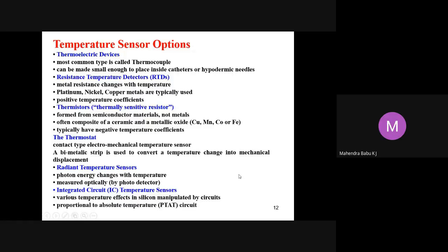When it comes to different types of temperature sensors, the options available for us are, first, thermoelectric devices. The most common type is called a thermocouple, which can be made small enough to place inside catheters or hypodermic needles. Then resistance temperature detectors, RTDs, where the metal resistance changes with temperature. Platinum, nickel, and copper are typically used.